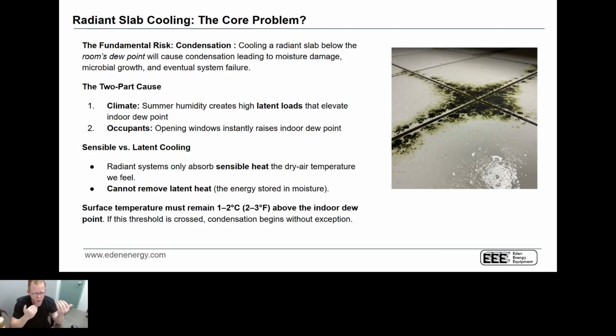As we look at it, we have to be focused on sensible and latent cooling. We have to recognize that radiant systems are able to absorb sensible heat, which is no problem, but there are better ways to remove the latent heat, which is the energy stored in moisture. And this would be true whether you're doing air to water or air to air, right? If we just look at a home right now, it's not an air to water system, it's an air to air system.